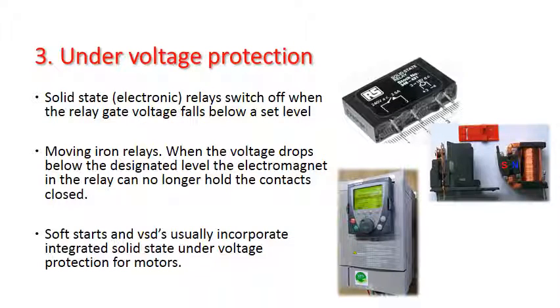Undervoltage protection. You think, well, why do you need that? Well, in some circumstances, not enough voltage driving a motor, for instance, is as bad as too much. So there are different solid state or electronic relays that will switch off when the gate voltage falls below a set level, and that will stop the equipment from working. There's mechanical or electromechanical versions as well. Moving iron relay here, you can see in the middle, and it does the same thing. When there's not enough voltage to produce enough current to hold the magnetism in the coil, the relay drops out.